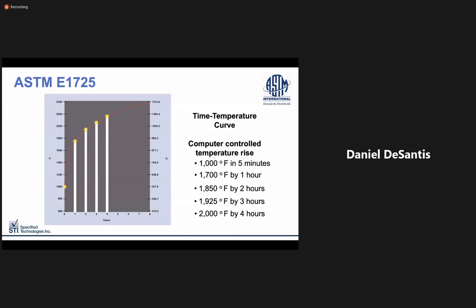They even use this time-temperature curve to evaluate the barriers themselves, to determine if gypsum wallboard assemblies can carry a fire resistance rating, for instance. This curve helps to achieve a consistent fire rating that serves as a baseline for all systems. Having a consistent test acts as a yardstick to measure against for all systems across all manufacturers.